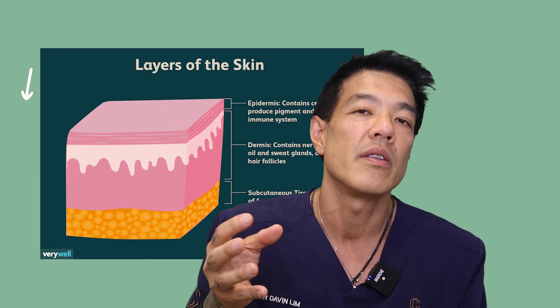Now, you can also use that to target your adipose tissue, in other words, your pre-platysma fat, which can be targeted using things like CoolSculpting, cryotherapy, or even things like liposuction. However, with this device, you can cause collateral damage of the fat, but at the same time stimulate collagen, and hence why it's useful around the submental area, in other words, the under chin fat. It is also very good for sculpting around the jawline area. Now, these certain areas, for example, like fat reduction of your nasolabial folds, your deep folds over here, and your buccal, not buccal fat, but your buccal area.